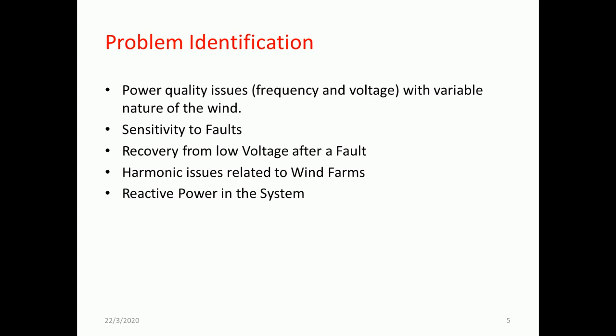A low voltage can also isolate the generator from the mainstream, and again this wind turbine generator should be equipped with LVRT characteristics. What do you mean by LVRT characteristics? That is low voltage ride through capability. Harmonics are a major concern, a major issue in the wind sector. Now what are harmonics? Harmonics are integer multiples of the fundamental frequency. A distorted waveform gives us an indication that the system is having harmonics.